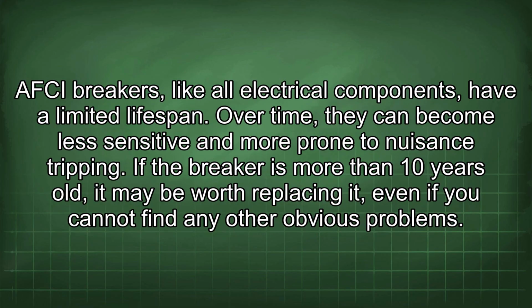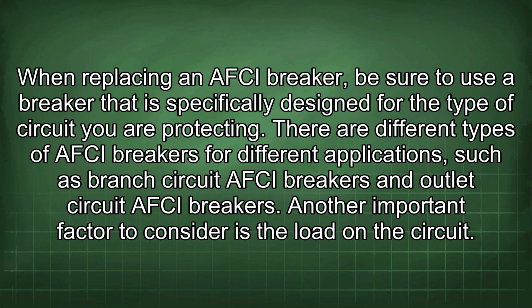AFCI breakers, like all electrical components, have a limited lifespan. Over time, they can become less sensitive and more prone to nuisance tripping. If the breaker is more than 10 years old, it may be worth replacing it, even if you cannot find any other obvious problems. When replacing an AFCI breaker, be sure to use a breaker that is specifically designed for the type of circuit you are protecting.